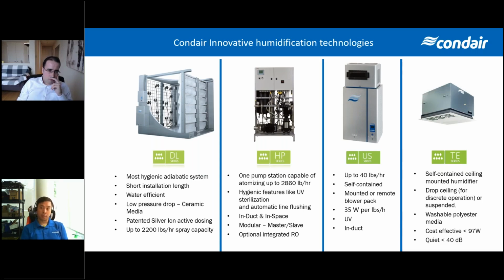And then for the smaller computer rooms or server rooms, we actually do have standalone systems. So for example, the US, which is our ultrasonic series that maxes out at about 40 pounds an hour. Really ideal for small computer rooms, small server rooms, where you just need a minimal amount of humidity and potentially some cooling as well. And then a new product for us this year is what we're calling the TE series, which is a small ceiling mounted humidifier, which is an evaporative system, but fits within a drop ceiling space. So if we're limited on install space, or if you don't have a ducted air system where we can retrofit a larger cold water system, that might be a perfect fit.